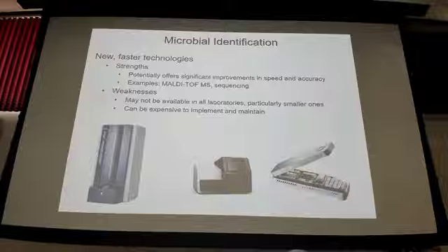The different peptides that are ionized in the process have different unique masses and different charges, so their mass to charge ratio matters when they hit this detector plate on the far end of that vacuum tube. That detector plate will convert those signals into a profile that can be read out as a spectrum and then associated with different types of bacteria.